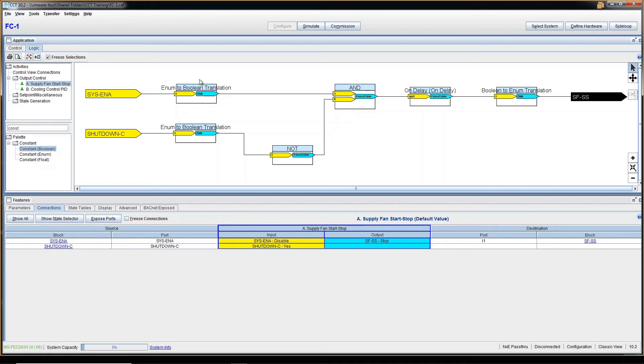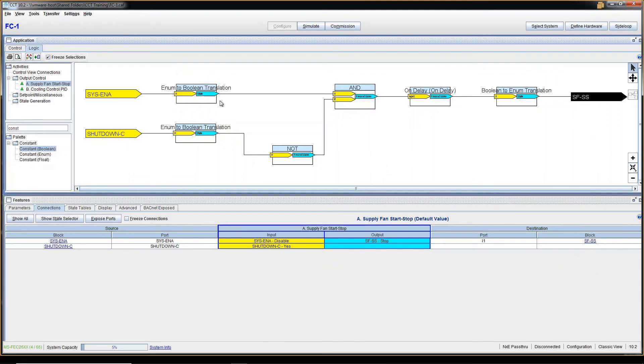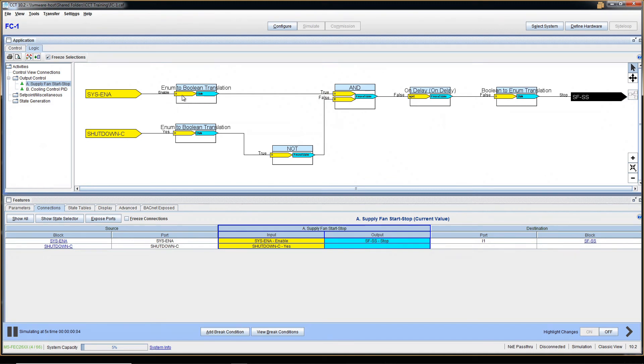In order to do all the logic programming, we need to translate everything into Boolean — the two-state system. So after System Enable there is an Enum-to-Boolean translation, because that's the only way to connect System Enable to an AND gate or NOT gate. Same thing with Shutdown Command — there's a translation. The translation tells us that the input Disable/Enable maps to false/true, so it can go into Boolean logic. Let me run a simulation quickly so you can see the actual values change — you can see Enable is being translated into True.